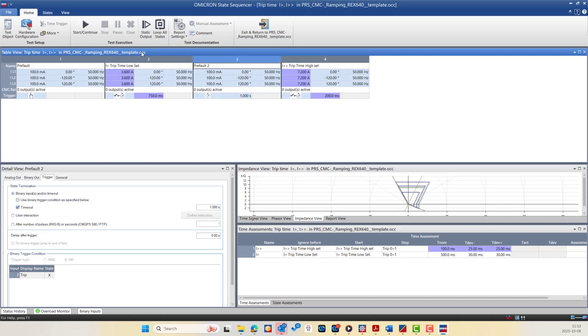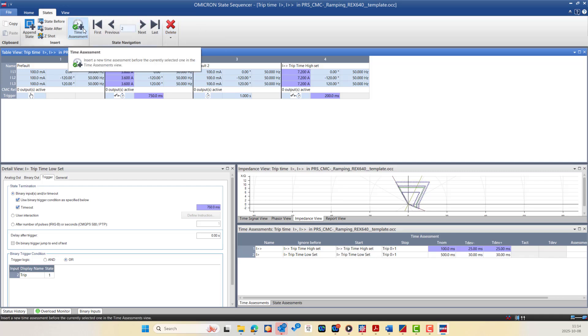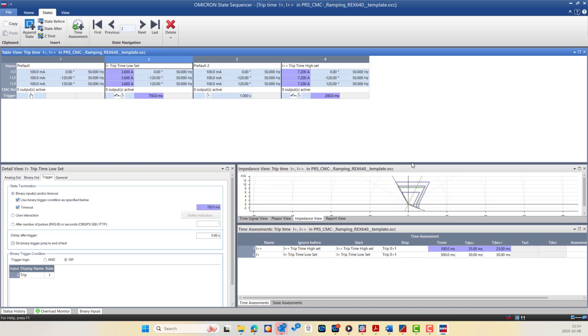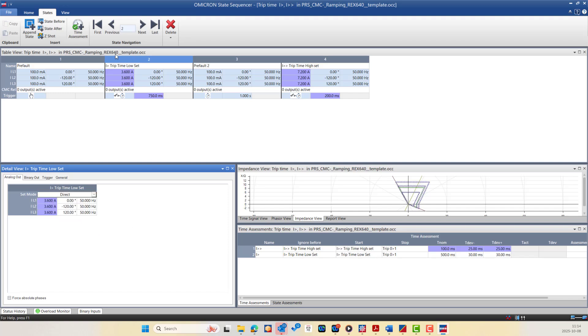As you can see, we have the Home ribbon as in all modules, but here there is also a Static Output option if you need to output a value for a long time without making a sequence. We also have the State Navigation Bar from which you can navigate between states or delete states as needed. You can add a time assessment, add a state before or after, append a state, or add an impedance shot. In the Impedance View, you can add impedance shots based on line length, fault loop, and constant impedance, with the current source set from the Analog Output using constant current, constant voltage, or constant source impedance modes.